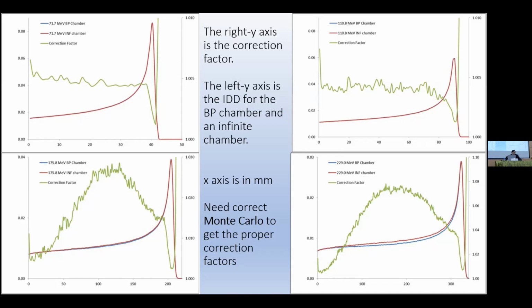So being able to do a proper Monte Carlo to say, this is what my system is actually going to look like, and then do the measurement to verify that and know where the differences are, and be able to explain that. Because then your measurement data is what you put into that treatment planning system in order to do calculations for patients. So all that is to say that knowing these characteristics is why chamber size is important. And the bigger the chamber, it might seem better, but there are also other things that may go wrong with larger chambers, meaning maybe the wall itself, you now get positional uncertainties.